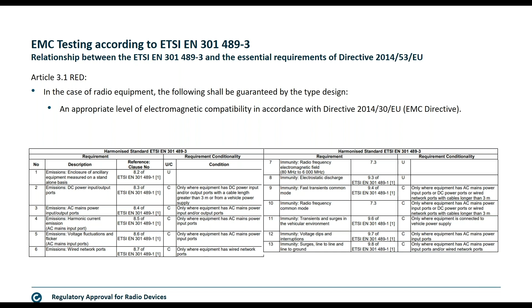Okay, short introduction to EMC testing. In general, all EMC testing for devices without radio interface also applies to devices with radio interface. The main difference is that your device still needs to operate in this radio frequency transmission or reception, whatever it is, whatever conditions have been applied during EMC testing. The overview here shall indicate just a few EMC tests that are applied to your device. First one would be ESD, electrostatic discharge. Your device has been, let's say, influenced by harsh voltage potentials between 4 kilovolt and 8 kilovolt, depending on whether it's a contact ESD or air discharge. We have conducted emission and conducted susceptibility.